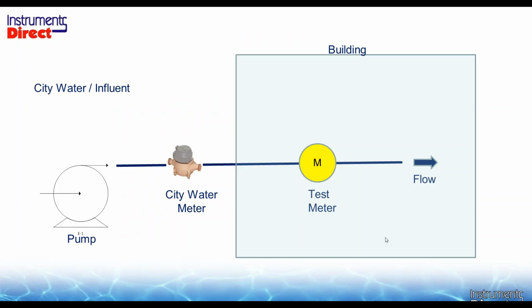Well, what we normally get is an inquiry. They'll have a city water meter outside. We'll go inside the building, in the basement, and they want a reference meter here. And lo and behold, our reference meter sometimes reads higher than the city water meter. And they'll say, my meter's wrong. No, my meter's right. A city water meter is a mechanical meter, and the older it gets, the slower it gets. So the worst thing you can do after complaining about your city water meter is say, city, please replace my water meter. I guarantee you your water meter bill will go up.